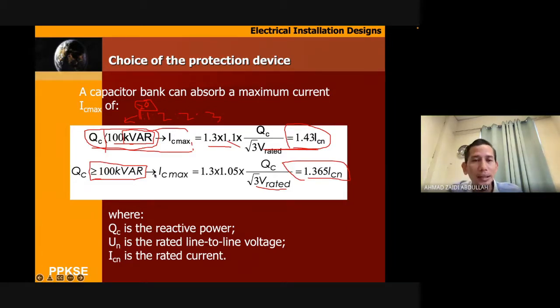Because the higher the value of the capacitor or QC, we need the margin to be lower compared to below 100 kVAR. The higher it is, the more dangerous it is. So we need to make sure that the breaker can work very fast. Okay.